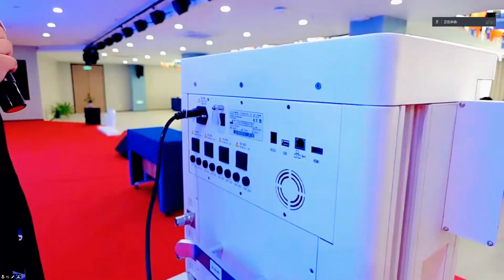And for oxygen, why do we always have two ports? Because oxygen is the driving gas for the system. So if we have two ports, you can connect one port with the central oxygen supply, and if you also have an oxygen cylinder, you can connect the other port with the cylinder. Then we can ensure that if one of them fails, the other one can automatically keep supplying oxygen to ensure the machine is running stably all the time.